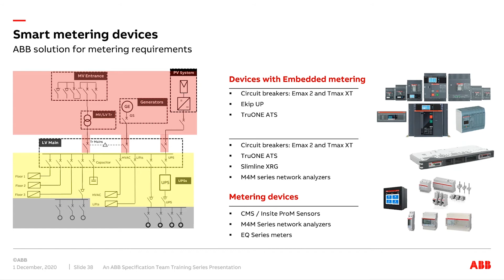The first example here shows a Greenfield installation, or a new installation. At the design stage this is relatively easy to achieve, as a lot of the components shown on the left-hand side will already be embedded into a new design. We're looking at air circuit breakers, molded case breakers, UPS systems, and integrating existing metering systems. As you can see by the red dotted line, it can all be integrated, say on a Modbus system, and taken back both to local monitoring and to a cloud-based platform.